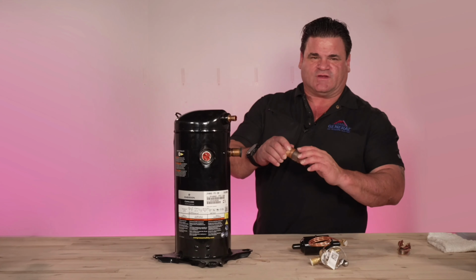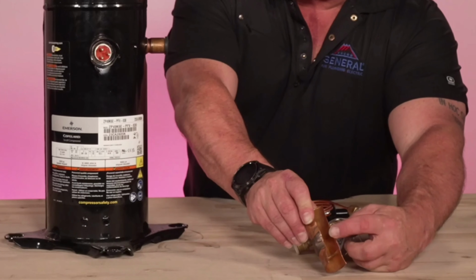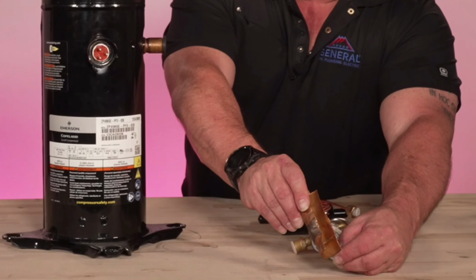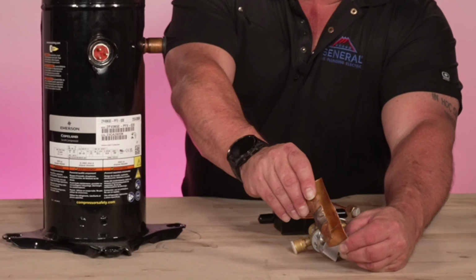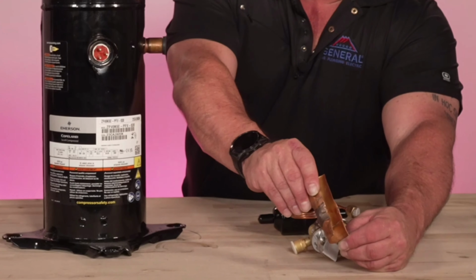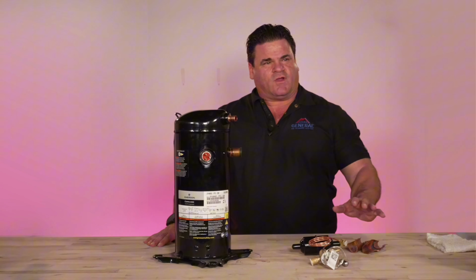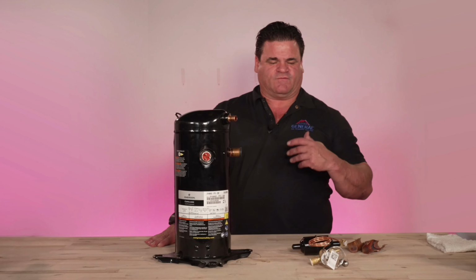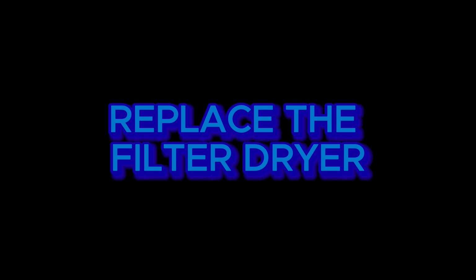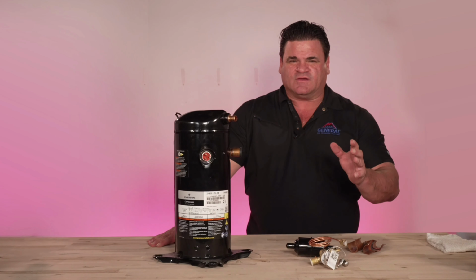This one, nitrogen, very similar outside. And if you can see, the inside is clean, right? No oxidation, no debris. This is why you always flow nitrogen. Not flowing nitrogen will wreak havoc on your system. So very, very important when someone works on your system, if they're going to open the system, they're going to replace the filter dryer. They're going to braze with nitrogen. And then the other step is they're going to pull a vacuum.